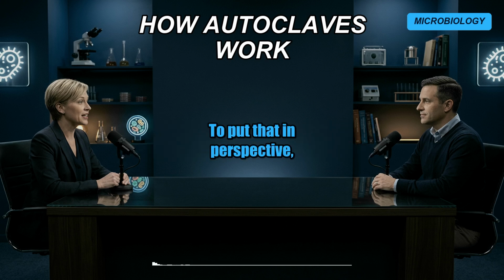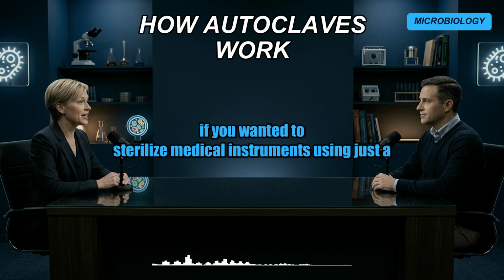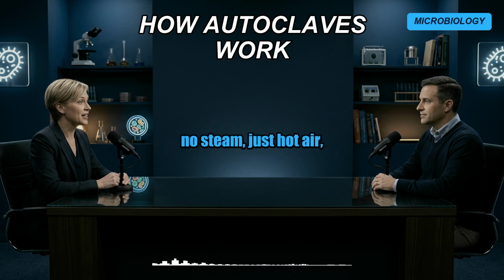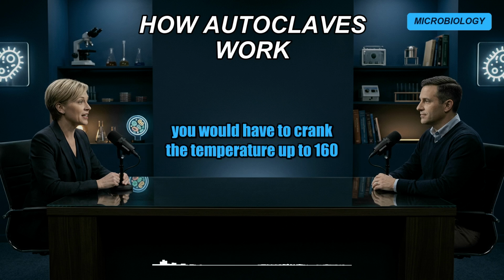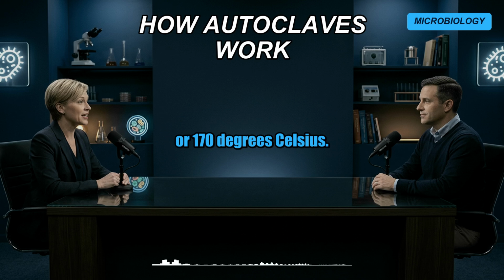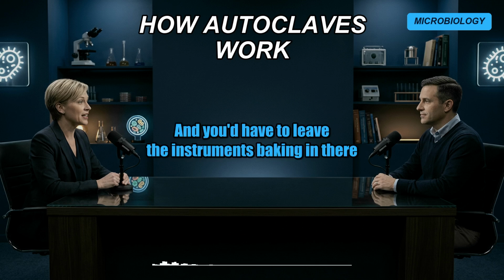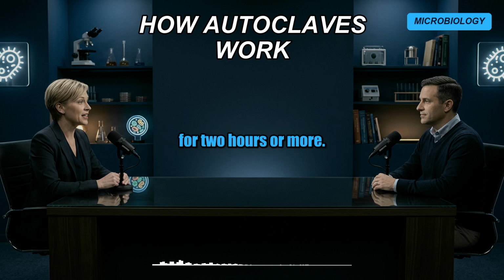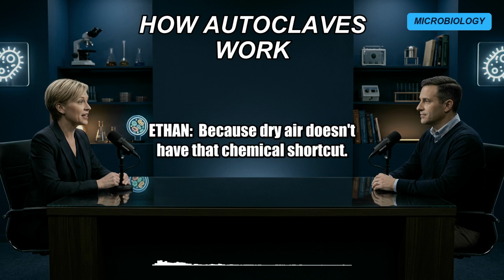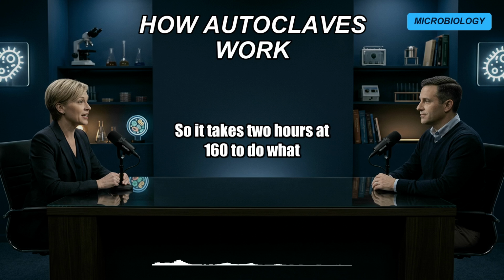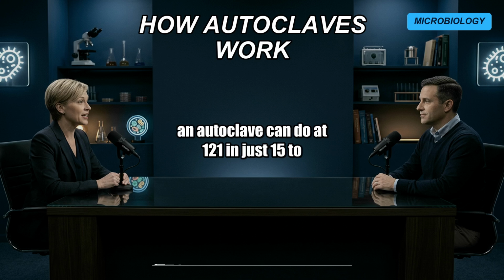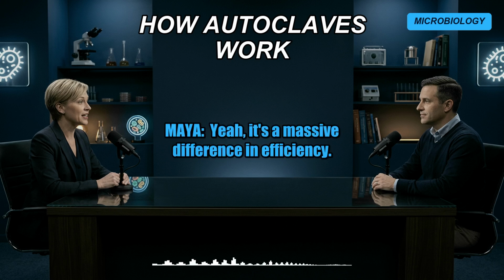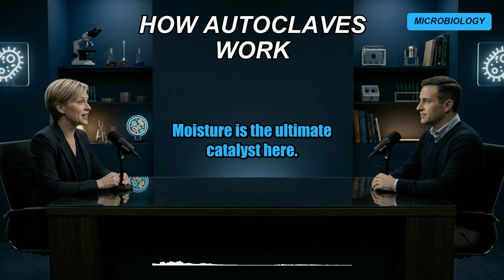Precisely. To put that in perspective, if you wanted to sterilize medical instruments using just a dry heat oven, no steam, just hot air, you would have to crank the temperature up to 160 or 170 degrees Celsius, and leave the instruments baking in there for 2 hours or more, because dry air doesn't have that chemical shortcut. So it takes 2 hours at 160 to do what an autoclave can do at 121 in just 15 to 20 minutes. It's a massive difference in efficiency. Moisture is the ultimate catalyst here.